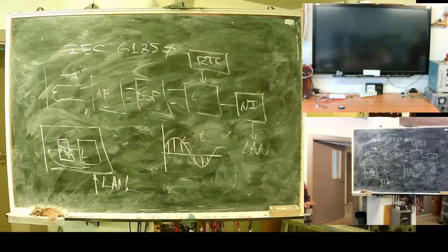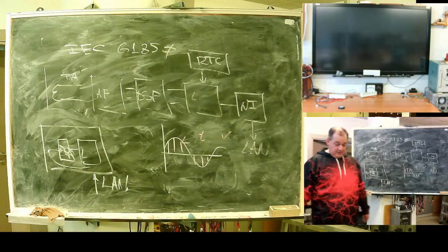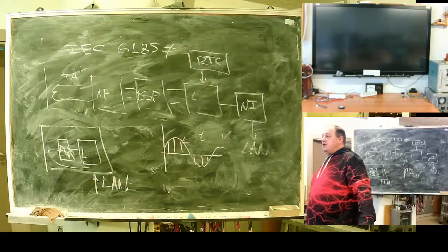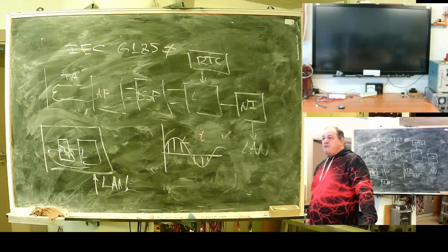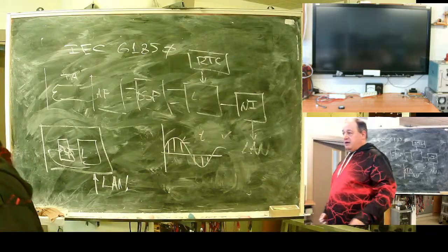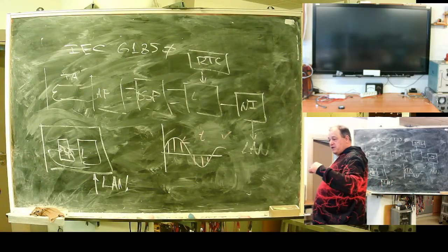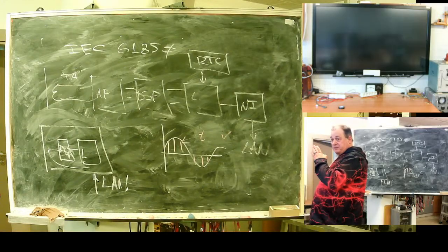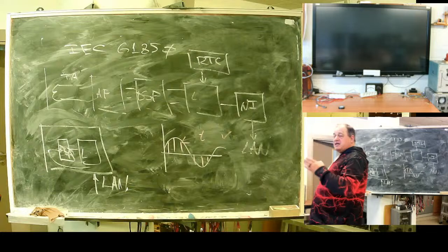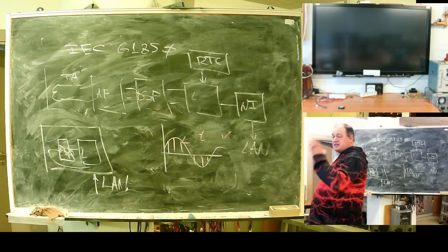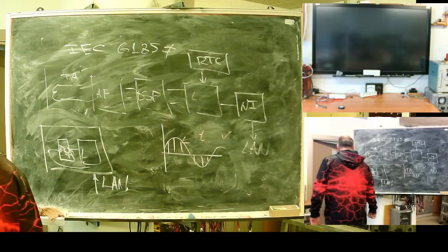So today, if we have a good budget, we can switch to a digital substation, where primary measurement units have their own initial signal processing stage, and are connected via local area network, so we receive time-stamped values from them, and they are shared. You can have as many devices as you want, even 200 devices, and these devices obtain measurements through the local network. It's a modern idea.